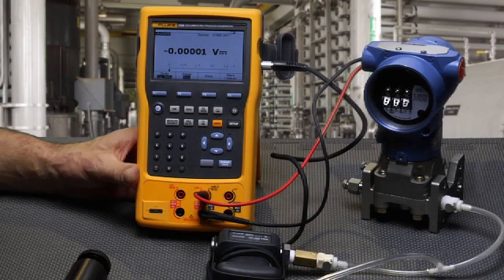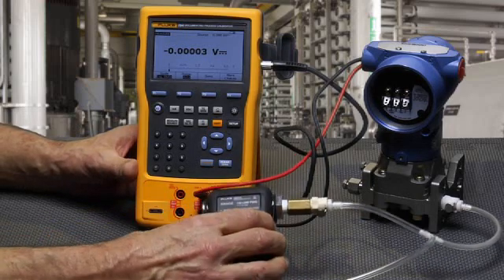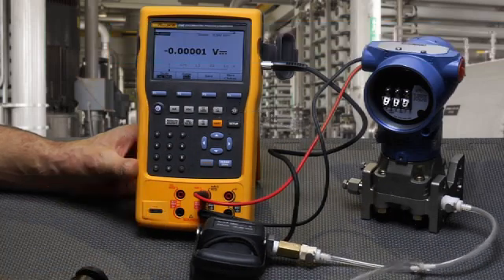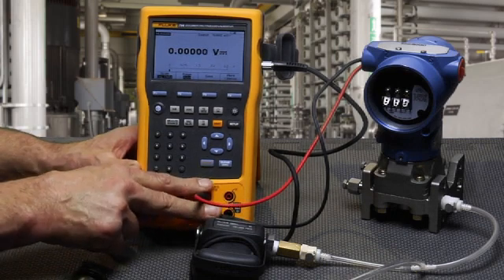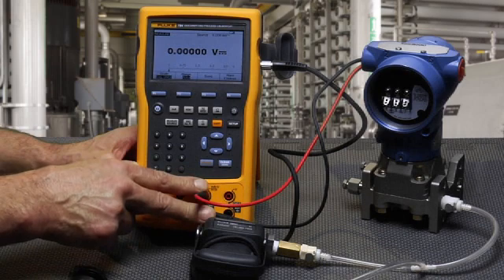I'd like to demonstrate how to calibrate a Rosemount 3051 HART Smart Pressure Transmitter using the Fluke 754 documenting process calibrator with HART built in. The calibrator will be measuring pressure applied to the input of the transmitter. Pressure will be sourced using a hand pump. The calibrator will measure the milliamp signal and power the transmitter on the center milliamp jacks, as well as switch in the 250 ohm resistor for communication.